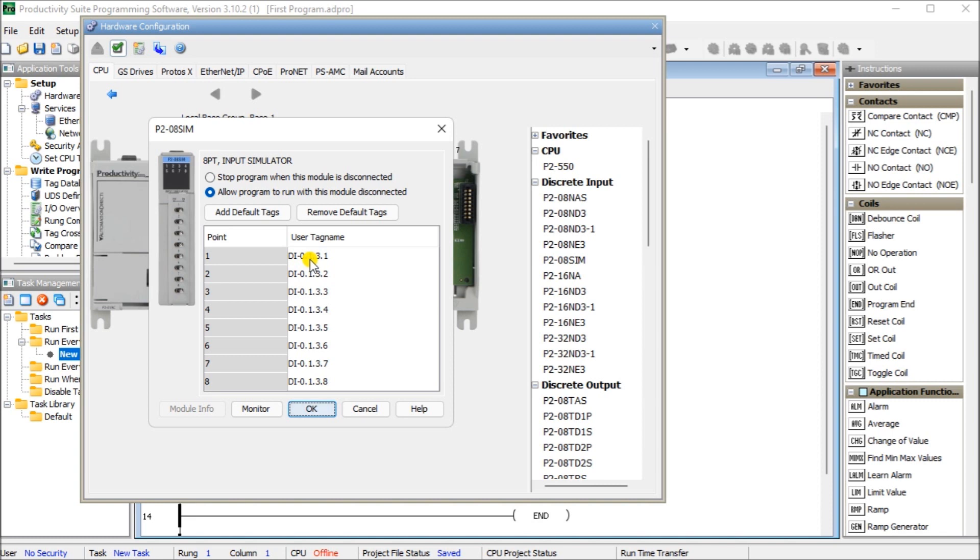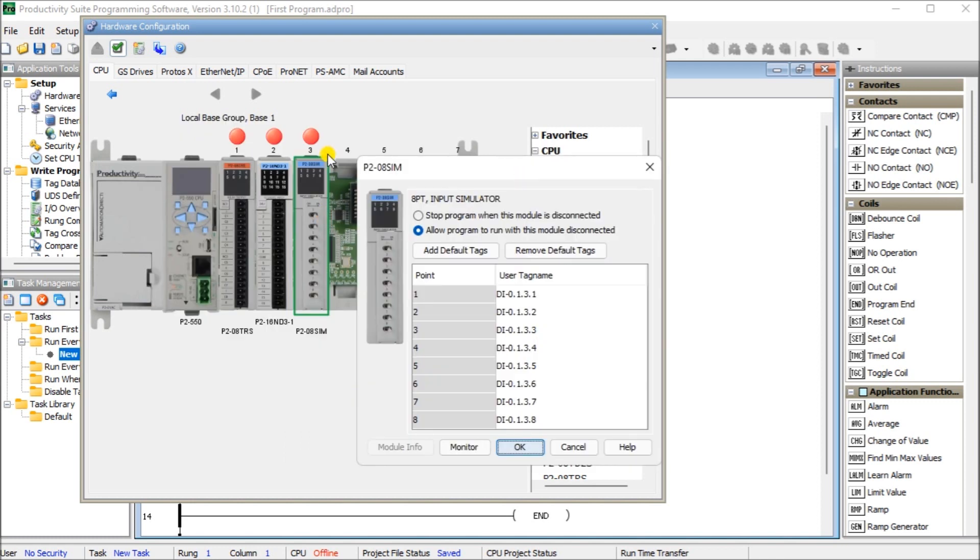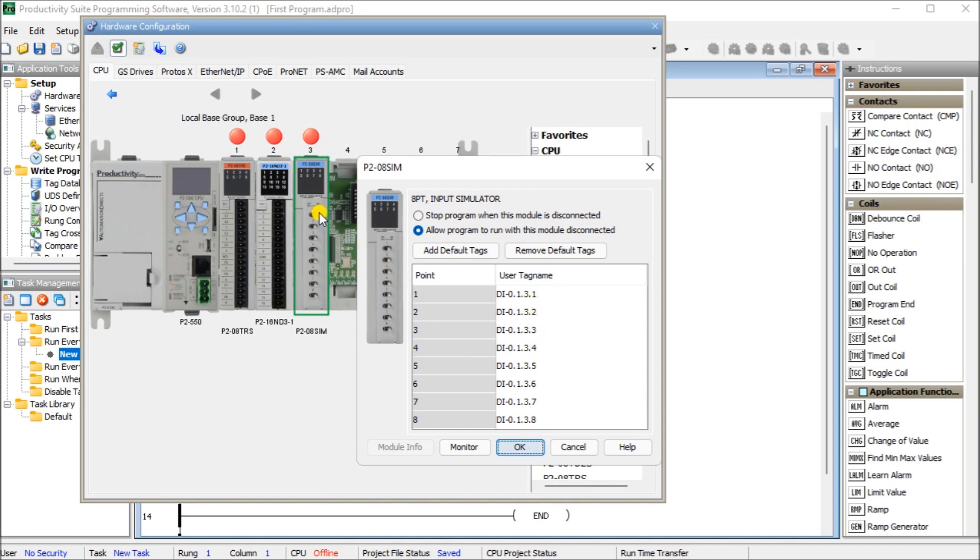Next is your slot number, which is three. And if I move this over, you'll see that it's on slot number three is our simulator card. And then the last one is the item number or the bit or the I/O point of the unit itself. In this case here, number one, two to number eight, which represents those switches one to eight. So that's how the default assignment gets done on our productivity 2000 controller.